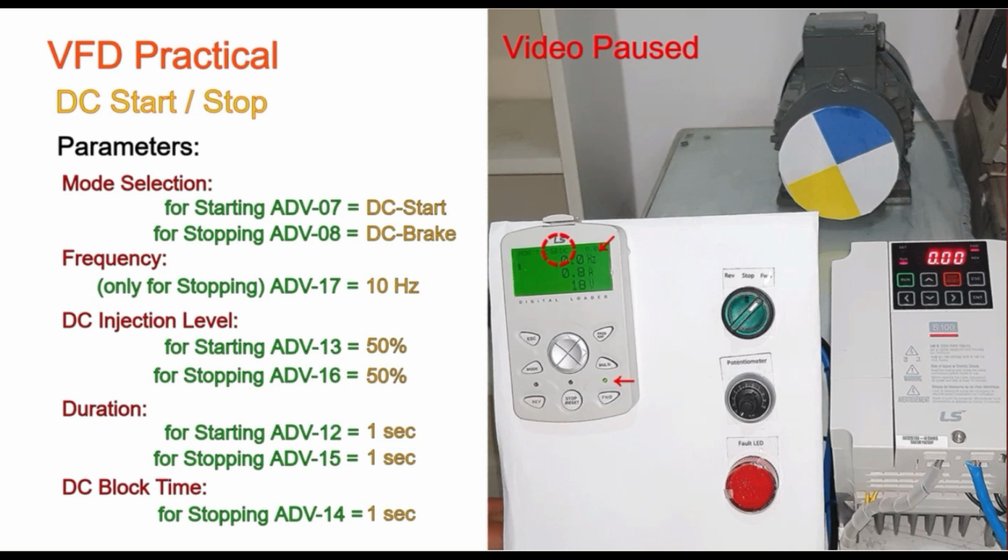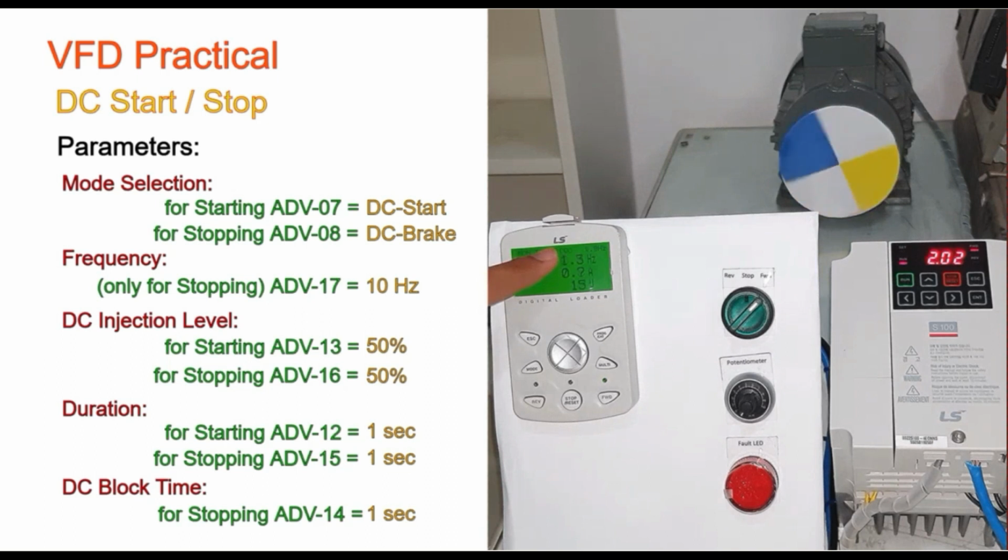What is the practical effect at start? We will see in detail later. If I resume the video, you will notice the VFD will apply DC voltage for 1 second. After the DC start time expires, the VFD starts normal operation.